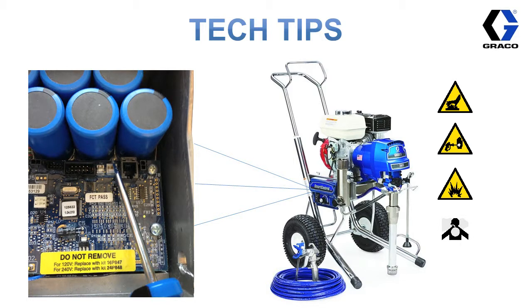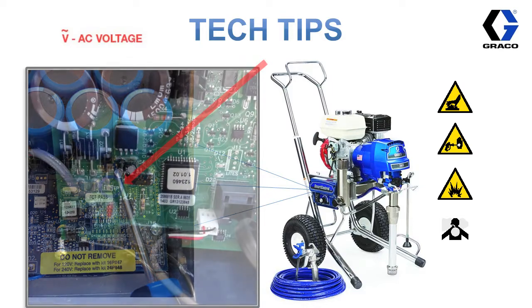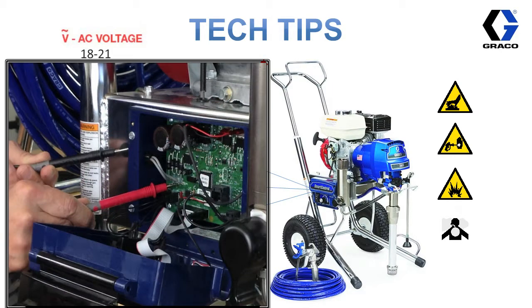What else? Check your AC voltage coming from the motor to the board. Okay, and how does one go about that? Take a meter and put it on AC volts. Is that an ohm meter? Yes. Okay. Ohm meter, voltmeter, and then you should get 18 to 21 volts AC coming off that motor coil. So that's what it should read if it's working correctly. Correct. Okay, and if it's not working correctly, what might we see on the meter? Anything under that, you're probably not going to have enough voltage to kick anything or to run anything else. Okay. And so if that's an issue, what's the fix? They would have to go to the Honda website, look up that motor, and get the specs and everything off of that.